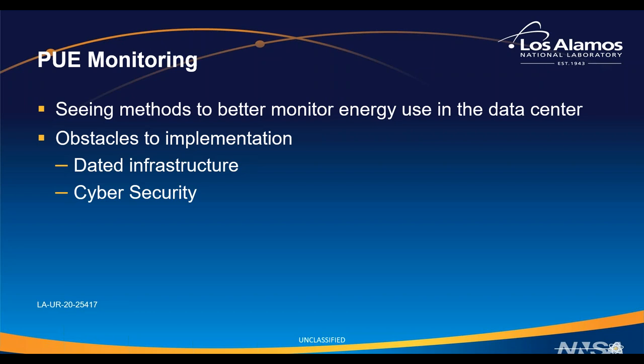To talk real quick about PUE monitoring with regards to some of our stakeholders: as Mike mentioned, some of our buildings are older 1960s type buildings. As a result, some of their infrastructure was constructed with low accessibility. Piping, HVAC systems were built in a way that weren't very accessible. So right now we're trying to find ways of sensoring some of these systems, retrofitting them, if you will, using sonic sensors to look at water flow and things of that nature. All of this is to go for PUE monitoring. We want to monitor how much energy is coming in versus how much energy is getting used and put back out into the environment. I listed on here a couple of obstacles to implementation.